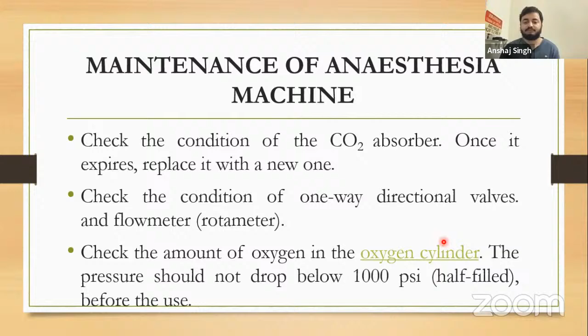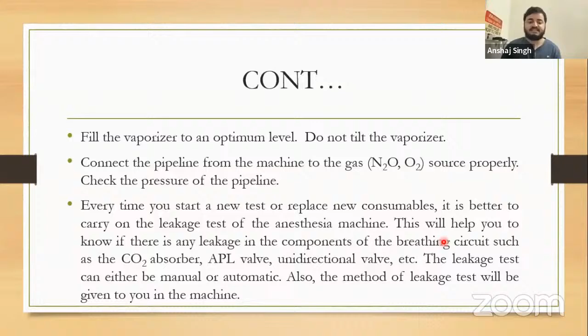Fill the vaporizer to an optimum level. Do not tilt the vaporizer. Connect the pipeline from the machine to the gas source properly. Check the pressure of the pipeline. Every time you start a new test or replace new consumables, it is better to carry out the leakage test of the anesthesia machine. This will help you to know if there is any leakage in the components of the breathing circuit, such as the carbon dioxide absorber, APL valve, unidirectional valve, etc. The leakage test can either be manual or automatic. Also, the method of leakage test will be given to you in the machine.